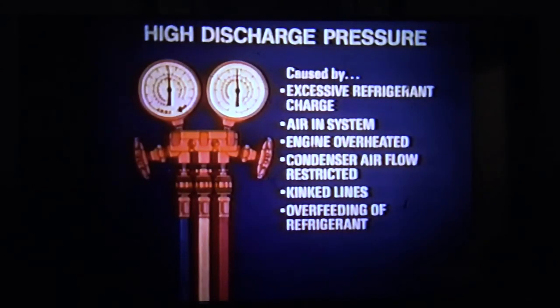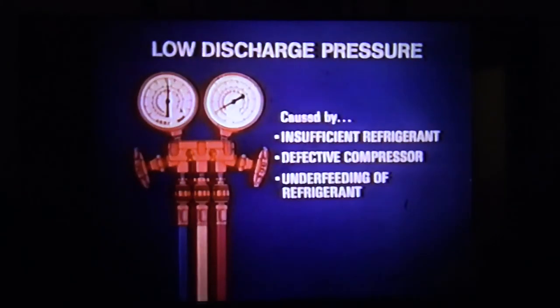Read and record the operating pressures with the engine running and compare them with the pressure chart in CTS 2622M. High discharge pressures can be caused by an excessive refrigerant charge, air in the system, an overheated engine, a restricted condenser air passage, kinked refrigerant lines, or overfeeding of refrigerant by the expansion valve caused by a valve stuck open or an improperly insulated feeler bulb.